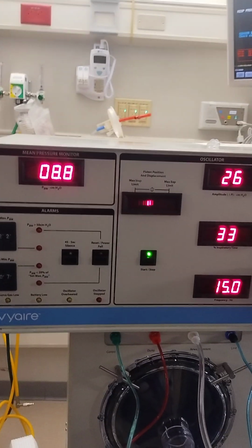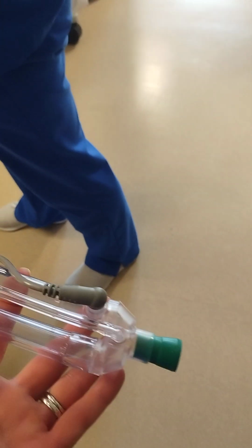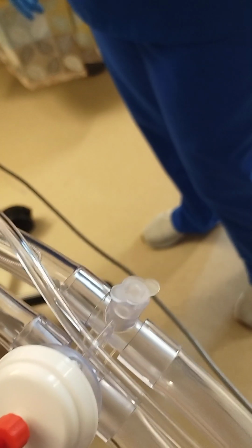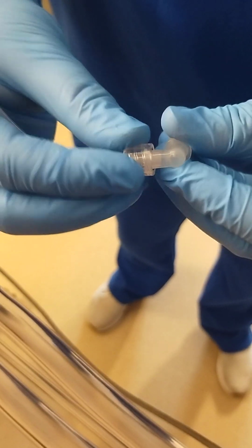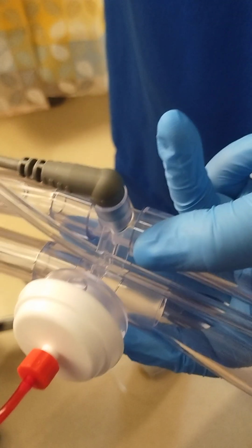And then the next thing we're going to do is place the sampling line in line with our oscillator. According to the NoxBox recommendations, they recommend moving your temperature probe here to this particular port, and then moving our NoxBox sample line here close to the patient. So first we're going to attach our elbow piece to the sampling line. Here we're attaching it to the sampling line, and now we're going to quickly remove our heater wire, and if you do this fast it'll maintain its pressure. If you've got two people you can actually do it without having to reset your mean airway pressure, but if it's one person, just switch it really quick and then repressurize.